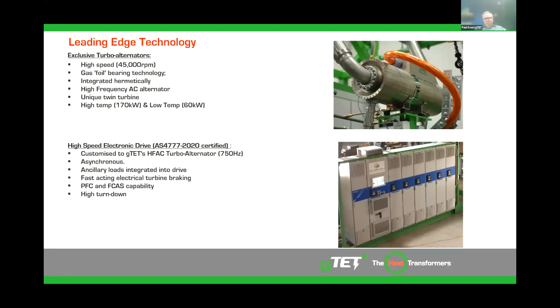Each turbo alternator is connected to a high-speed regenerative drive, outputting DC to a common bus that's then connected to a single AS4777 grid-certified inverter. The regenerative drive operates the permanent magnet alternator as a motor during starting and then adjusts the electrical load transfer to match gas pressure in order to maintain a constant operating speed once it's running. The integrated drive includes the system auxiliary drives, including the working fluid pump and cooling tower fan, which enables the ORC generator control system to select the most energy efficient operating point. GTET's ORC installations also manage power factor output of the generator to improve the site's overall power factor. A significant advantage in this asynchronous solution is the turndown it can provide that's often required with a highly transient waste to energy application.